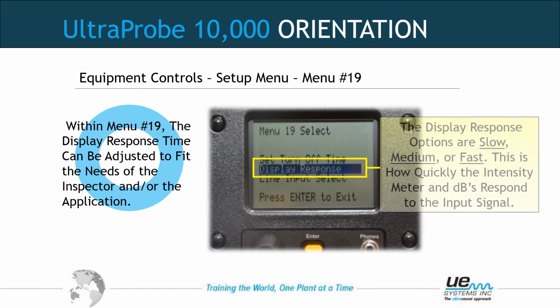Menu number 19, the next one down, is display response. It's defaulted to slow, which seems a little slow. You push the sensitivity button, it doesn't start to flash immediately. It takes just a split second. You may double click because of this. Fast, you'll watch the bar graph peg out every single time it hears a sound. Medium seems to be the way everything should react. So display response as a suggestion would be medium.